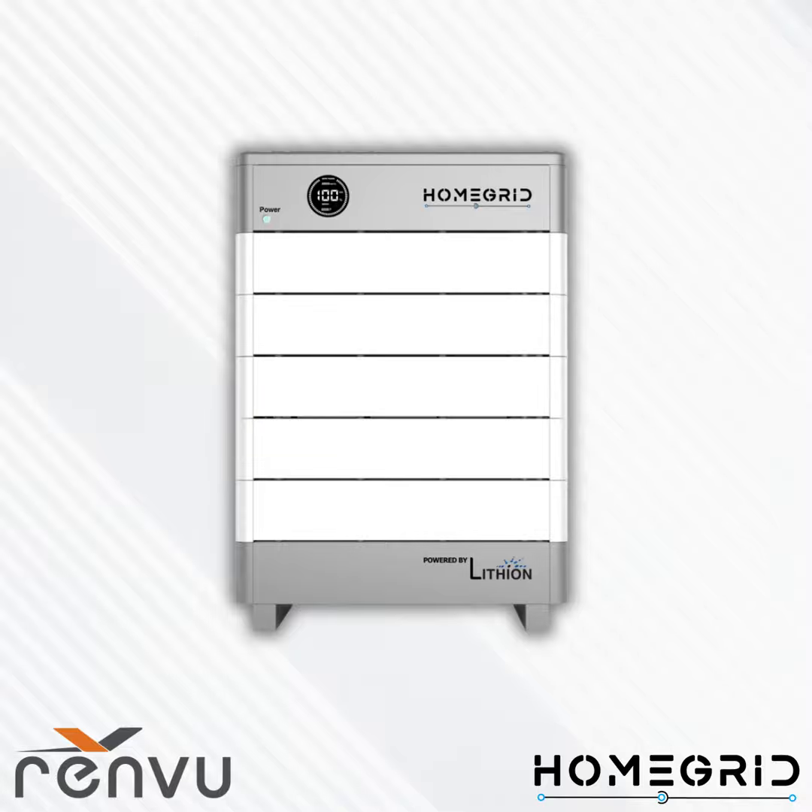The HomeGrid fleet is comprised of three products: our Stack Series low voltage, which is a 48-volt battery; the HV BMS, which is higher voltage — anywhere from 260 to 400 volts adjustable output using the same modules as the low voltage; and the HD Cube, which is basically an outdoor cabinet that is temperature controlled for both heating and cooling, IP65 rated. You can store up to four stacks, eight modules high in each cube, with up to 153 kilowatt-hours per cube.